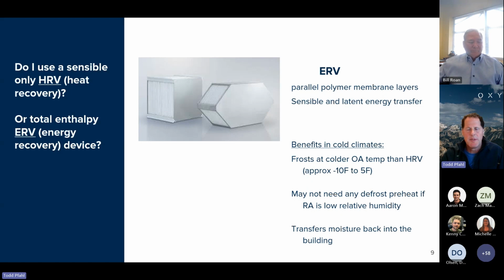The ERVs are total enthalpy recovery. These use a polymer membrane, at least the newer versions, where we have, again, these layers of basically a thick plastic, if you will, that transfers not only sensible temperature, but also the latent energy. A benefit of that in cold climates is that our core frosts at lower outside air temperatures. We typically see frosting not occurring until the outside air temperature is around 0 degrees or 5 degrees. In fact, if you're building RH on that design day of 0 degrees outside is 20 or 25% relative humidity, we probably would not need any type of preheater at all. So it makes for a much more energy efficient system.